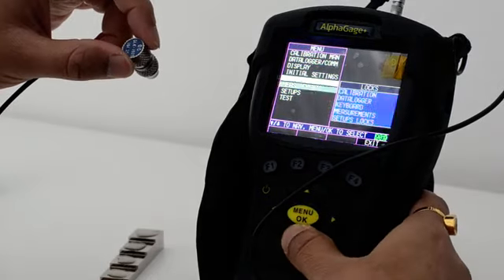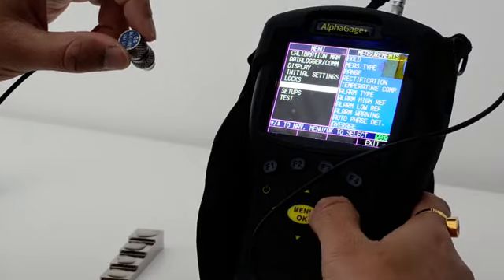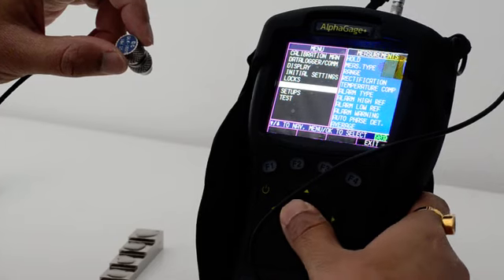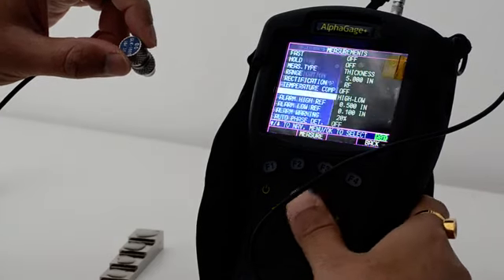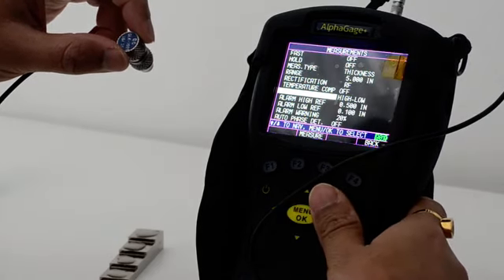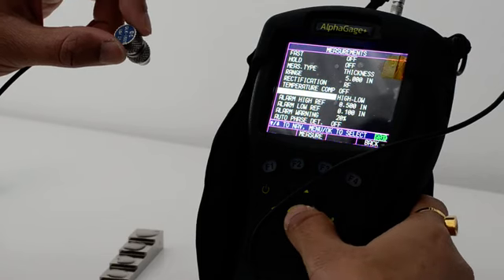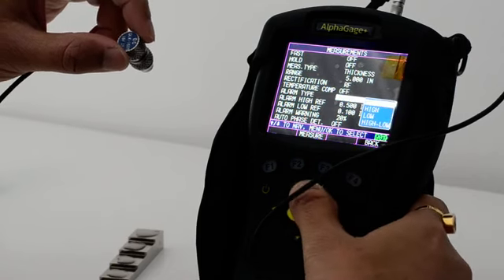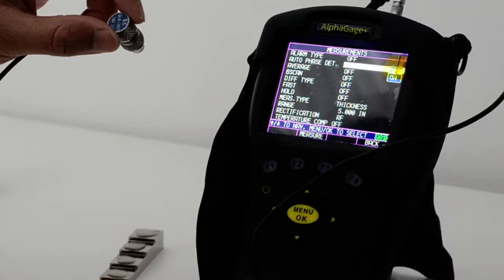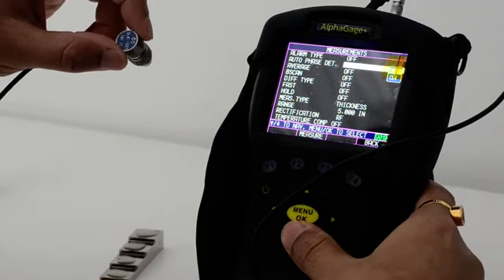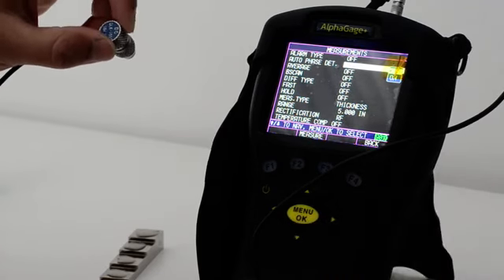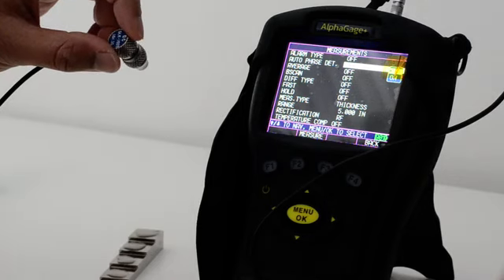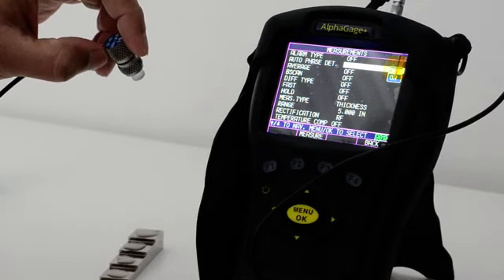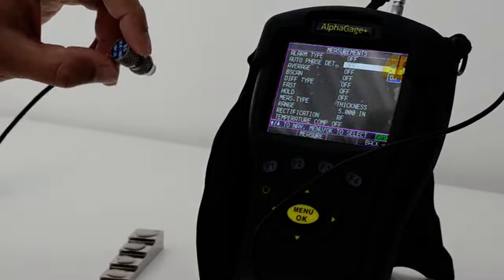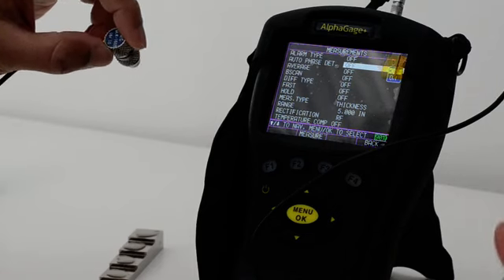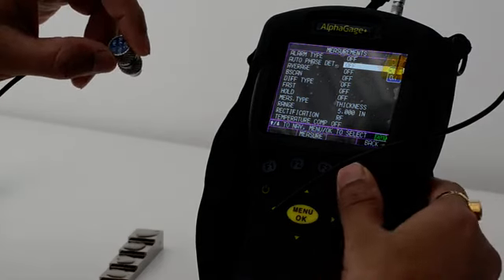There are logs, and then there are measurements. So measurement is the section where you set up the alarms. Right now my instrument was having some alarm, which is the high and low type. So if I want to switch it off, I can switch it off, or you can make it a high alarm or low alarm. So many people use a low alarm. In some cases, if you want to make an alarm for say 20%, you can do that in this section.